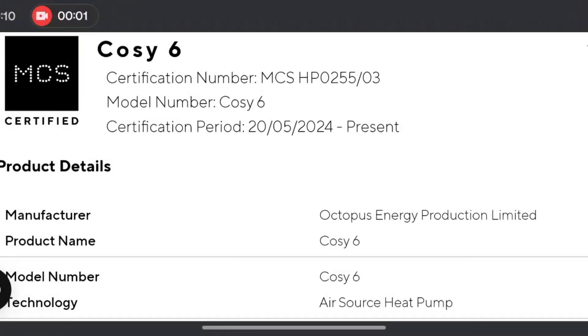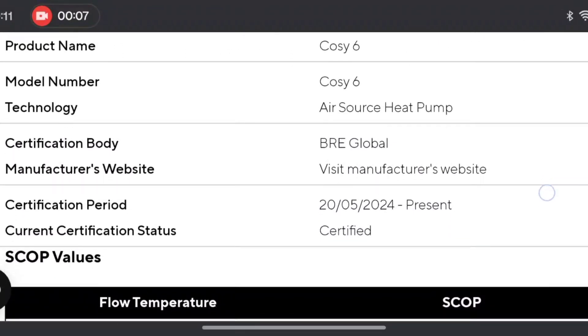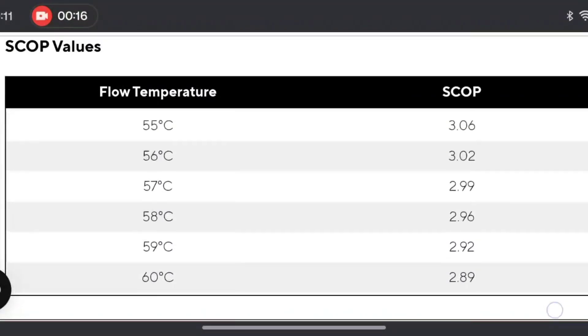In my previous video about high temperature heat pumps, I got a bit of flack for referring to the Cosy 6, but there's been a bit of an update. It's now on the MCS database, so it's been tested under lab conditions, and you can see that it's not very impressive. These figures are pretty poor.